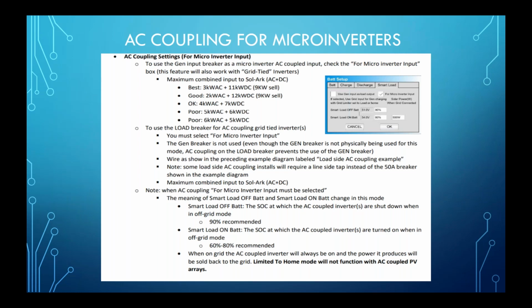Not to worry here. In our manuals, there are a number of wiring diagrams. You've probably heard me say a couple of times already in this presentation that the Sol-Ark inverter is very versatile, very flexible, and enables you to say yes to a lot of different application types. Well, true statement. So when we went back to our manual, we have about 7 different wiring diagram examples. There is a wiring diagram example exactly for this second bullet here. In the manual, it's titled load side AC coupling example. It'll show you exactly how to do this. There are about 7 other wiring diagrams.